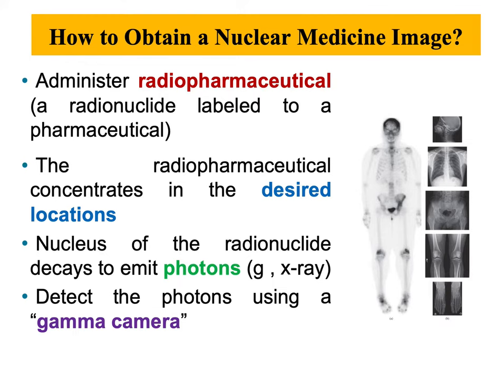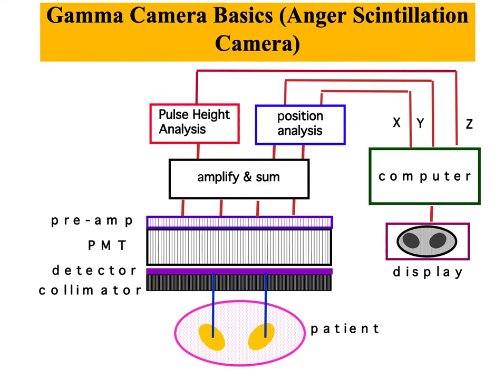The gamma camera consists of the following: it has a multi-hole lead collimator, and it has also a 10 to 25 inch circular, square, or rectangular sodium iodide scintillation crystal. It also has an array of photomultiplier tubes on the crystal, then a positioning logic network, pulse height analyzer, gating circuit, and a computer — as shown in the figure here. I will be talking about the functionality of each of these components in this video and in subsequent videos as well.